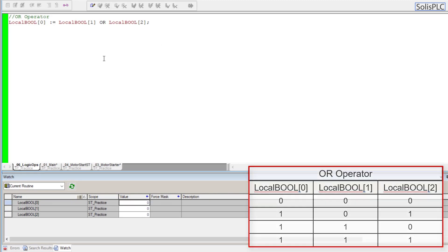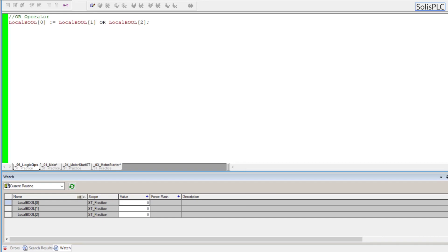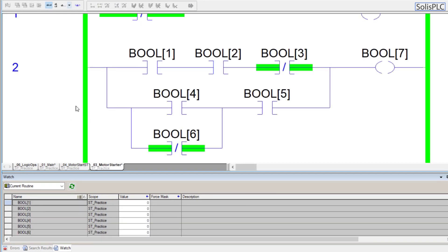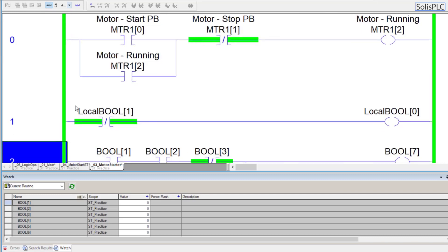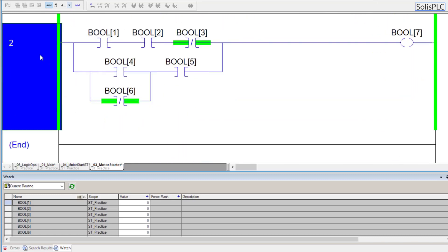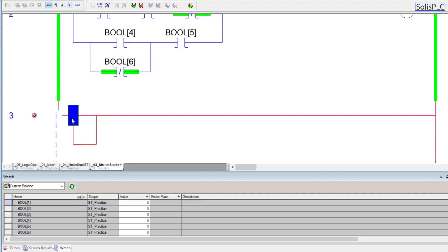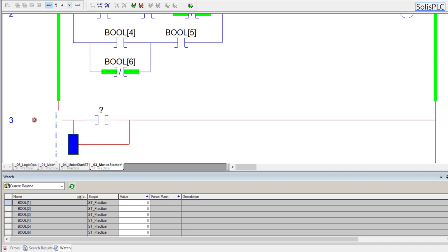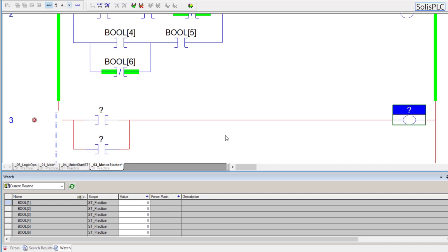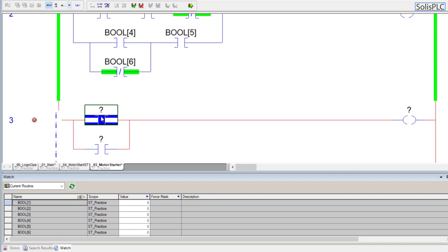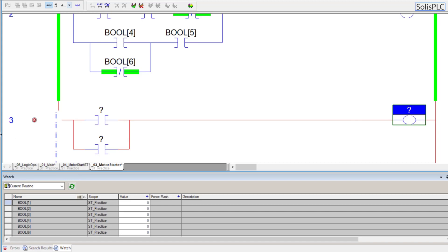This is an OR instruction. Going back to ladder logic, this expression would essentially be a branched circuit design. We can achieve the exact same result by using two XIC instructions followed by an OTE — the OTE would be local_bool_0, and both XIC contacts would be local_bool_1 and local_bool_2. This is essentially an OR branch: whether the top or bottom XIC evaluates high, the OTE will be set high.